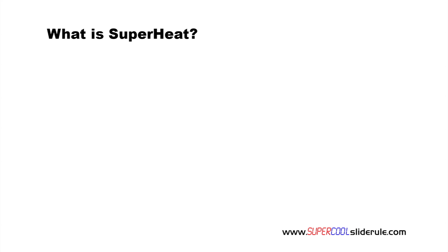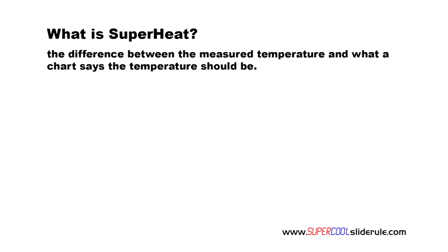All refrigerants have a relationship for pressure and temperature. So at any given pressure, there should be a corresponding temperature. Superheat is simply the difference between the measured temperature and what the chart says the temperature should be.